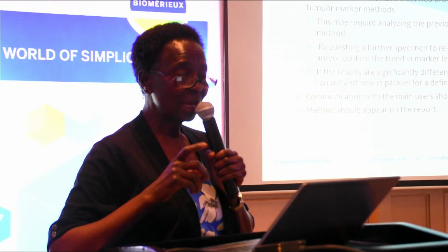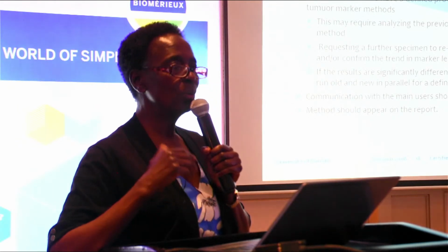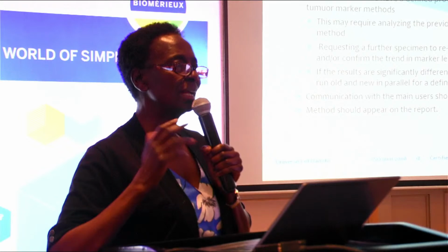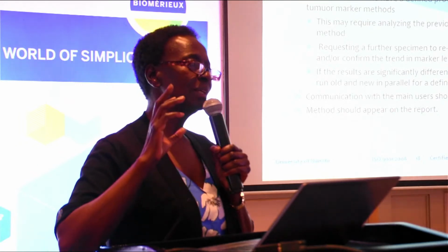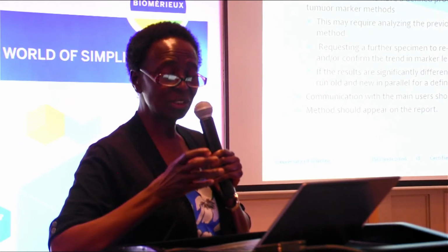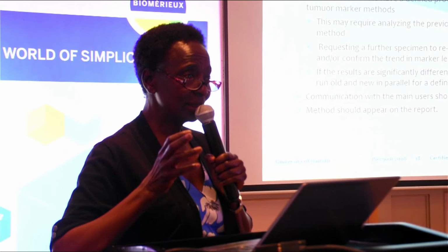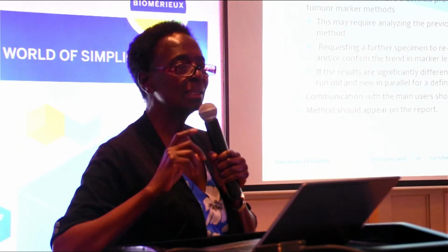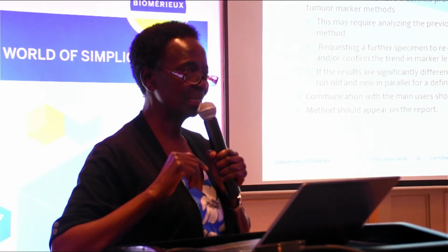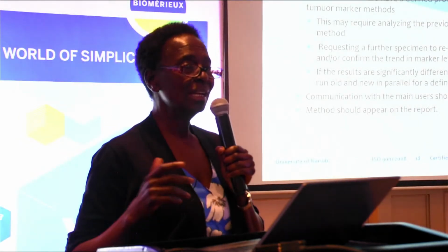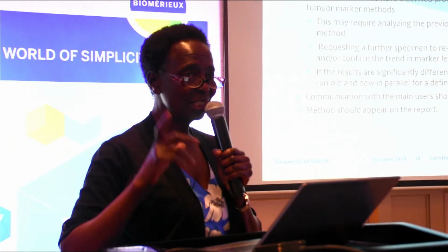Unfortunately, most immunoassays are not harmonized. What you will get for, say, CA19-9 on the Vidas will be totally different from what you'd get if you're using maybe an Abbott Alinity or the Roche platform. So not informing your users about the change may harm the patient, because suddenly the result may either go up or down. And remember I said the clinician thinks it is the patient who has changed. They don't think that something has happened in the lab.